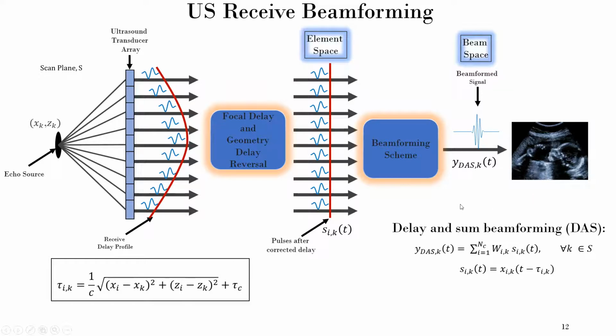And one important thing I want to focus on here is that you might naturally think, let's say this transducer has the shortest distance from this pixel, so it will be receiving the highest energy, right? Because as the distance increases, attenuation increases. So this transducer may not get the same energy as this transducer. So instead of just simply adding them together, you can even weight them according to the distance, for example. You can weight each of these signals according to the distance, let's say, and then sum it up. People call it apodization, and the same terminology that a digital camera uses, we call aperture there. The same concept can be employed here also to improve the image quality.